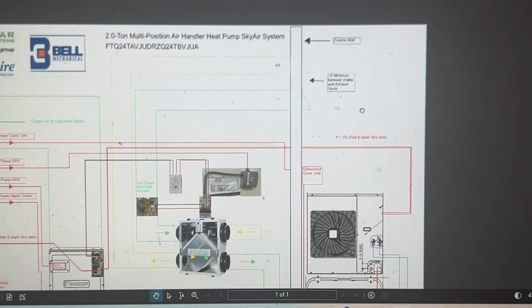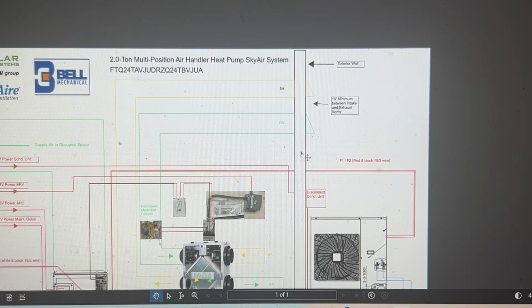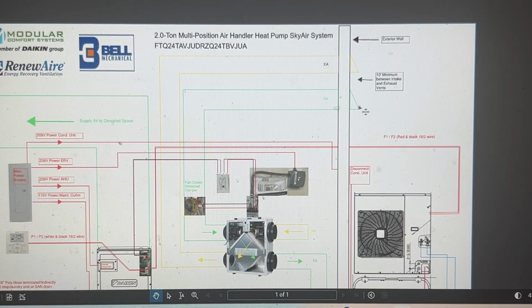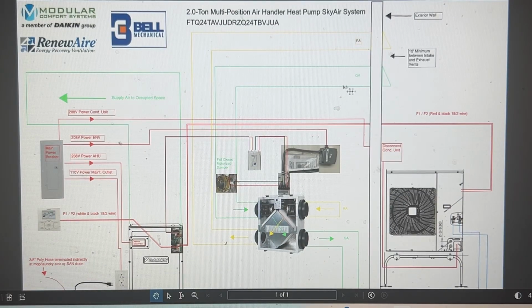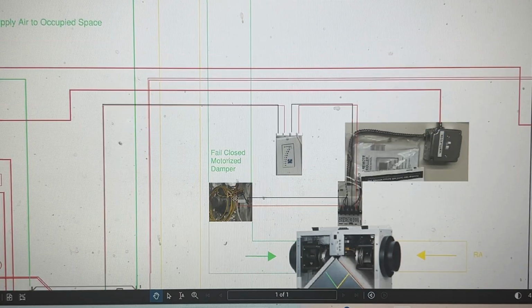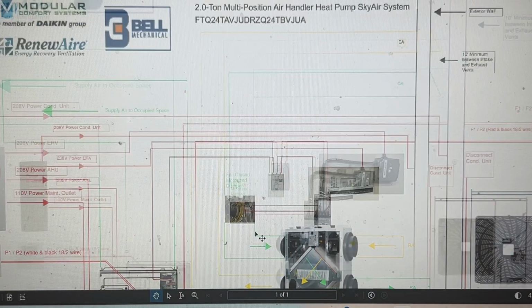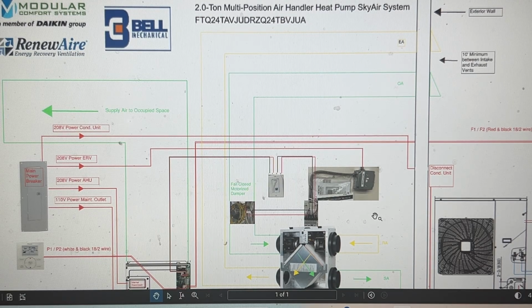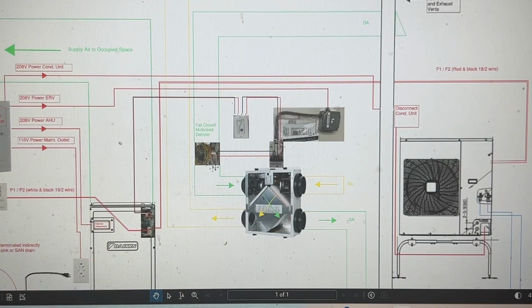So out here, this exterior wall is represented here. I've got an exhaust air and an outside air. Those two have to be 10 feet away from each other. We have a vent fitting on the outside, so that outside air comes in here. There is a motorized damper within that duct run. So in the event of a loss of power, that motorized damper fails closed so that you don't have an open 4 or 6 inch duct in the wintertime. That'll close it off so that it keeps the temperature as best it can.